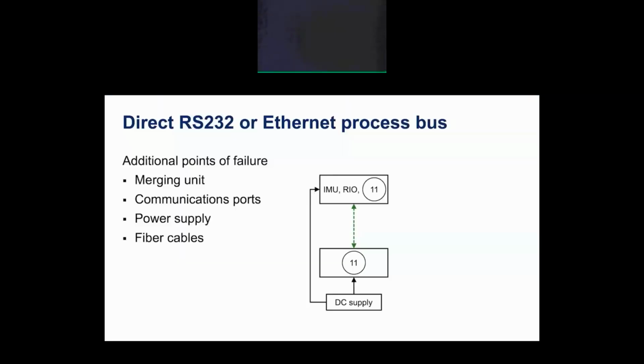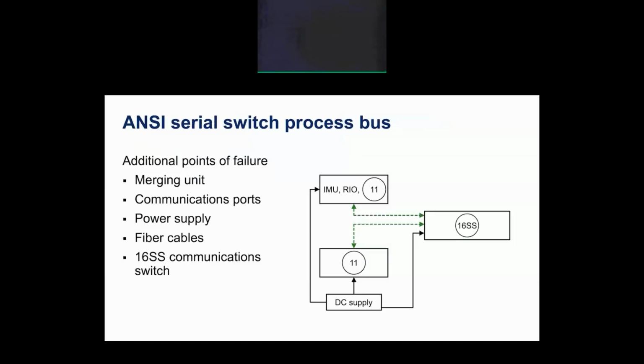Instead, we can connect those wires to a merging unit, ANSI 11, and then communicate the data between the merging unit and the relay using the digital cables. And this is the simplest connection, direct between the merging unit and the relay. When we need to send data to and from several devices, we use a communication switch.